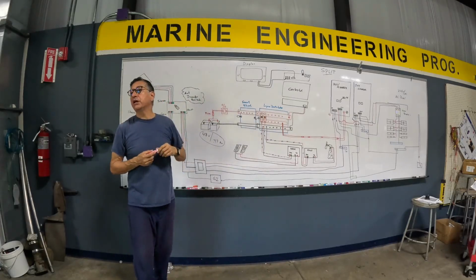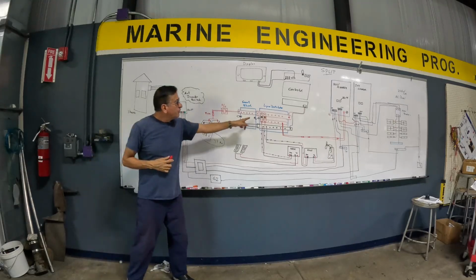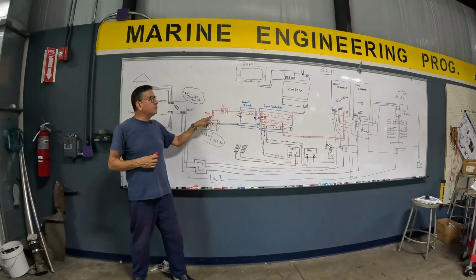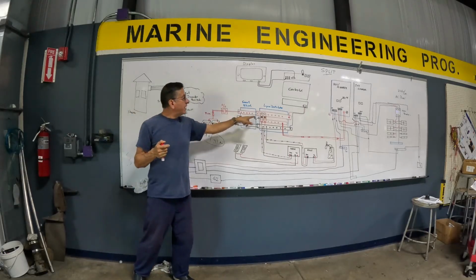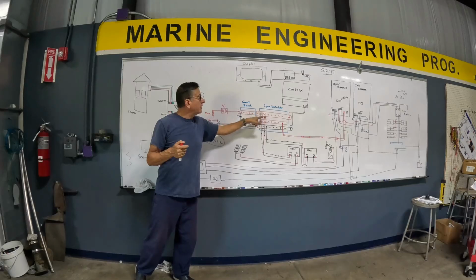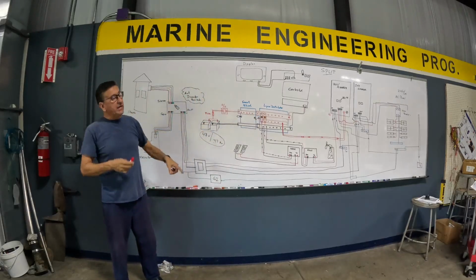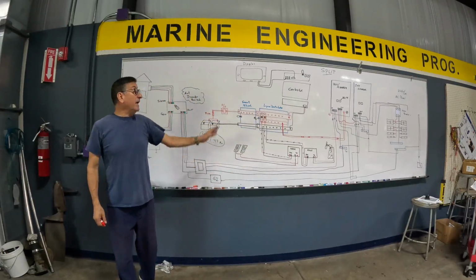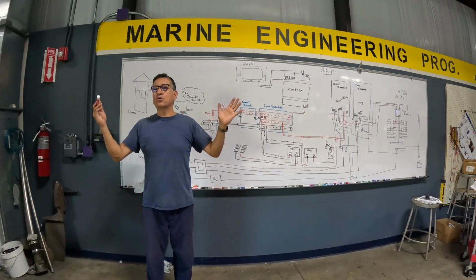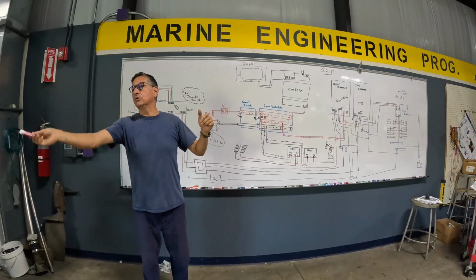Right now we are going to check the physical connection over there, and you see the mega fuses. Those mega fuses are different from those main fuses. I want you to take those pictures because in the future you need to buy mega fuses to connect both positive bus bars. And I am going to explain what is the function of those mega fuses. They protect the link distributor with overcurrent protection, doesn't matter if that current is coming in or going out.